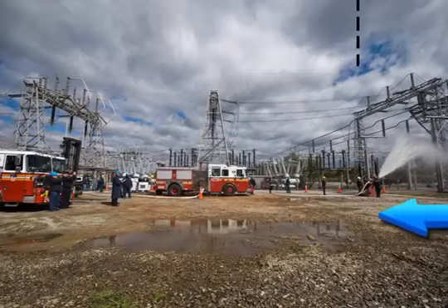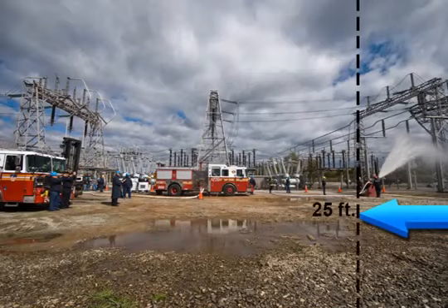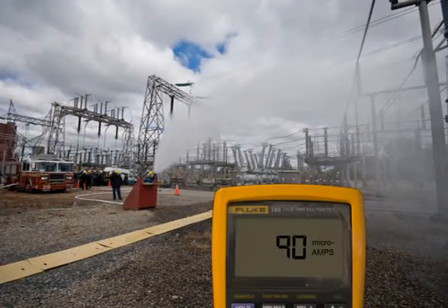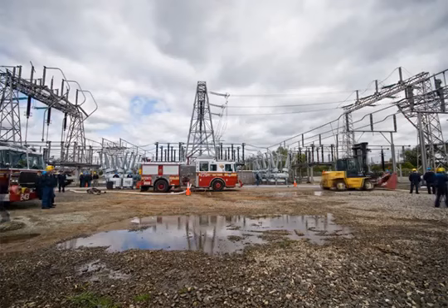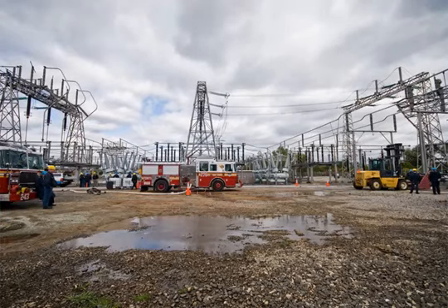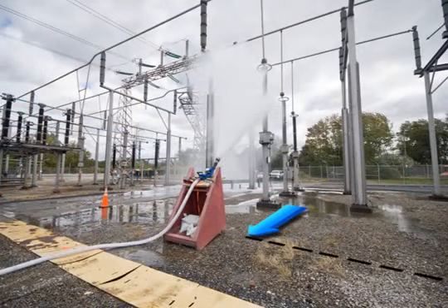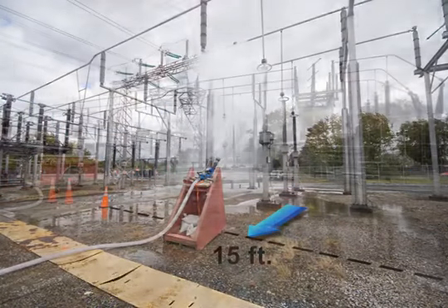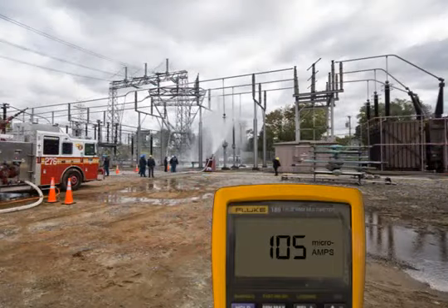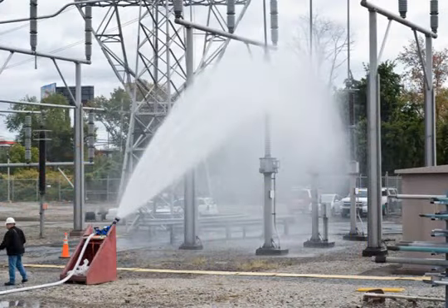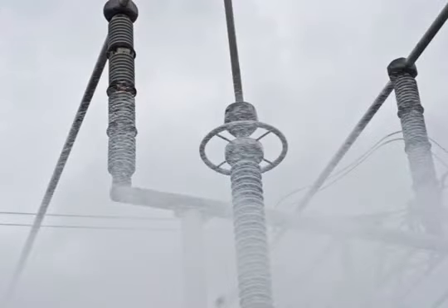We began the test at the 25-foot standoff distance from the conductors, and the readings varied from 80 to 90 microamps. We continued to move the stand closer in order to identify any significant changes in leakage. At the 15-foot mark, there was a minimal increase to 105 microamps. This indicates that the fog pattern is the safest method of delivery.